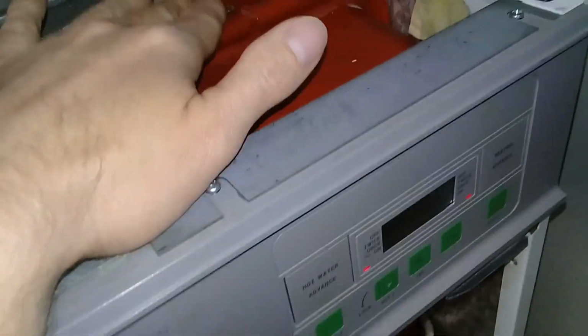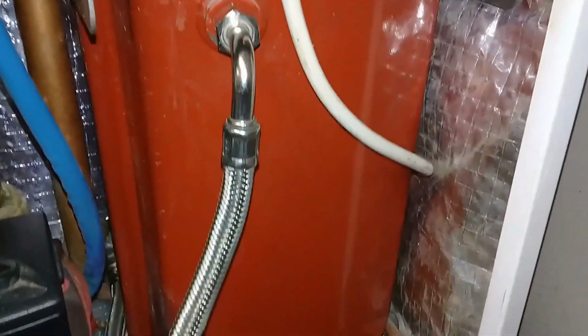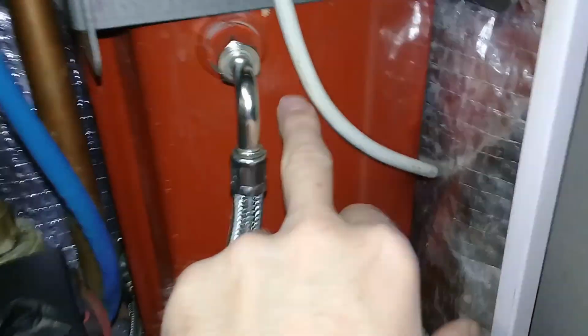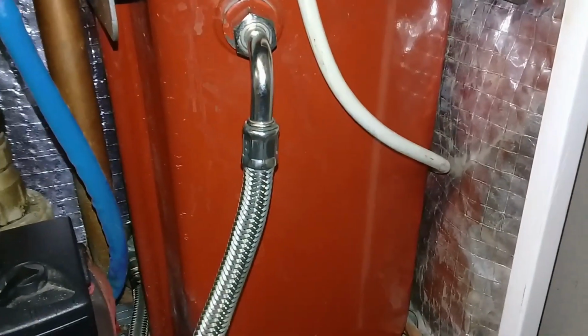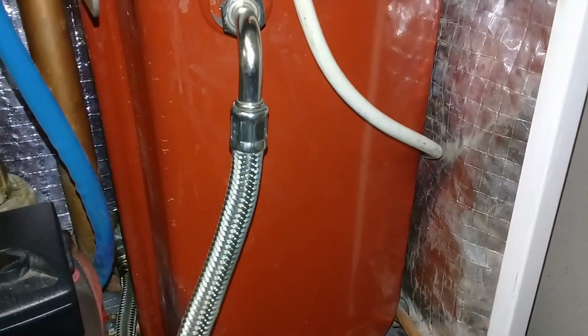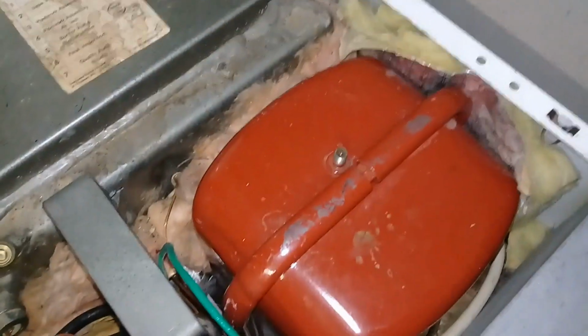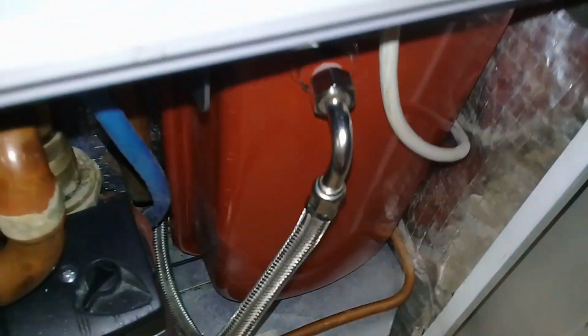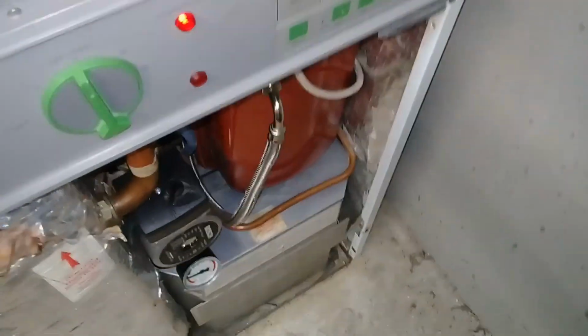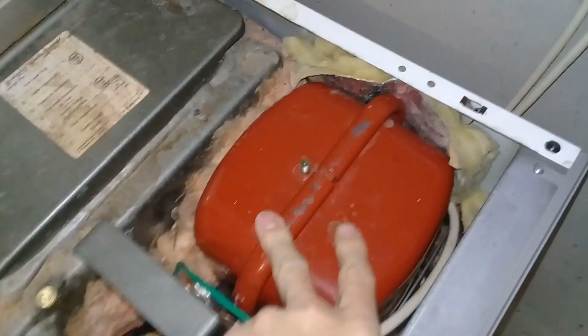So then I decided to take this out. This is quite easy to take out. You just take this off and pull it out. So I pulled it out, and doing that, I'd say it was three quarters full of dirty water. I emptied it as much as I could, which was difficult, and then I attempted to blow it up at the valve. Blowing it up at the valve, basically air just comes straight out here, which is wrong. So yeah, I've ordered a new expansion vessel.